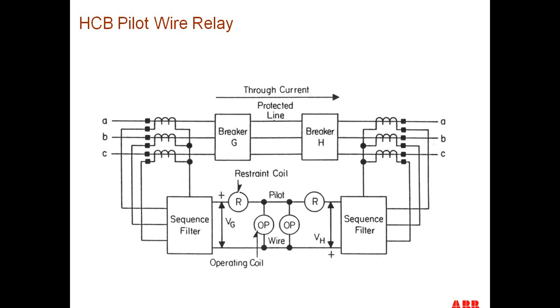The problem with this approach, though, was that the relay could only be used with this pilot wire, which is twisted pair. And most of the problems with the relay were dealing with this twisted pair, where the twisted pair would become shorted or open-circuited, or it would be out of the utility's control and controlled by the local telephone company, and they would stop even supplying the twisted pairs and would just supply fibers instead. And if the stations are too far apart from each other, you can have station ground potential rises between one station and the other, which would induce a current on the pilot wire.